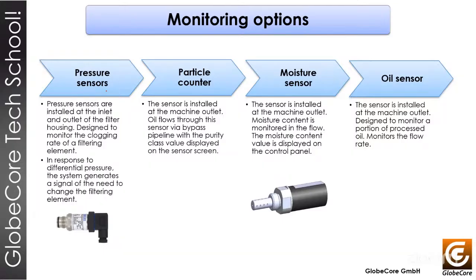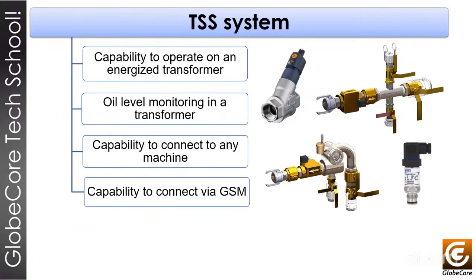And the oil flow sensor is designed for monitoring the rate of oil passing through the machine. That will help you to know how much oil is being processed by your machine in specific times. As I mentioned before, the TSS system is one system that helps you to connect the machine with the transformer energized. And one important thing is the TSS system can work with other machines. We can connect this kind of system to every kind of thermal vacuum and dehydration machine.